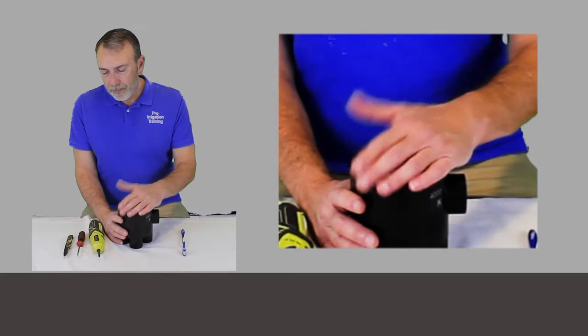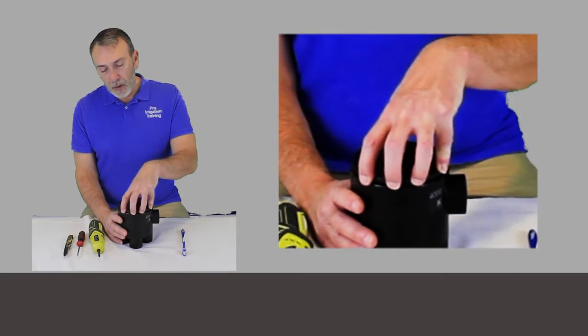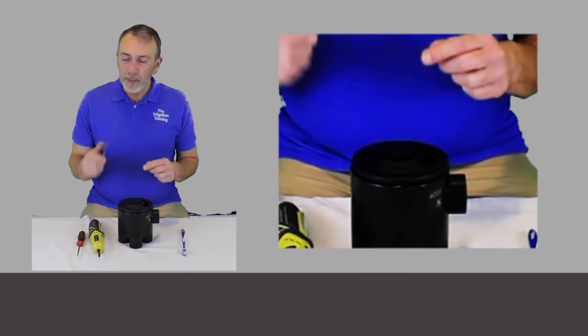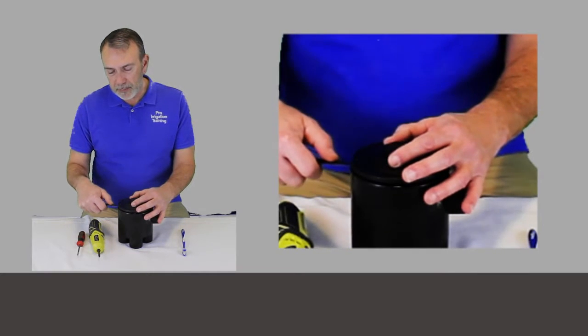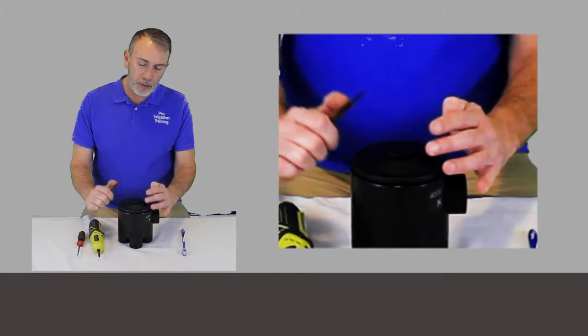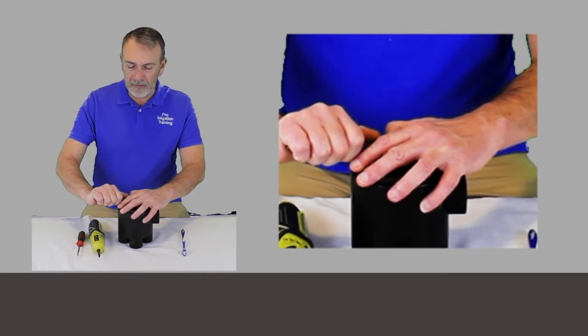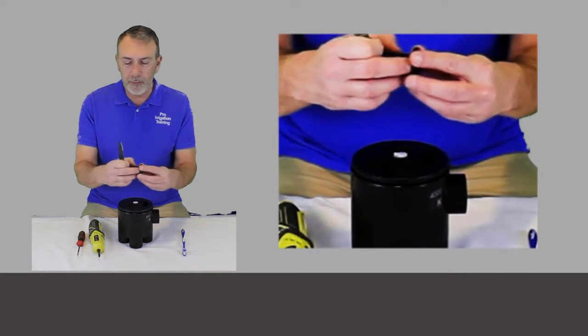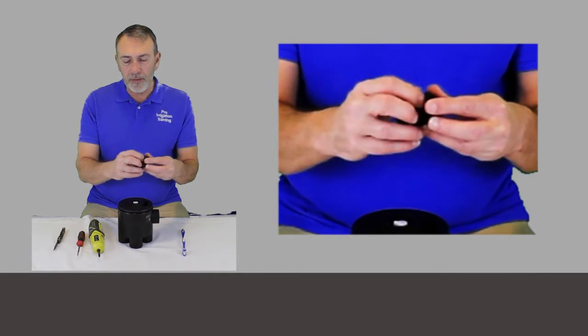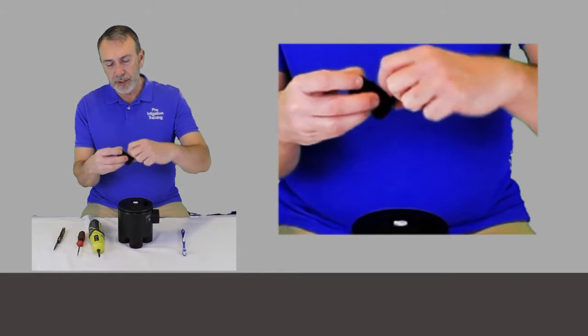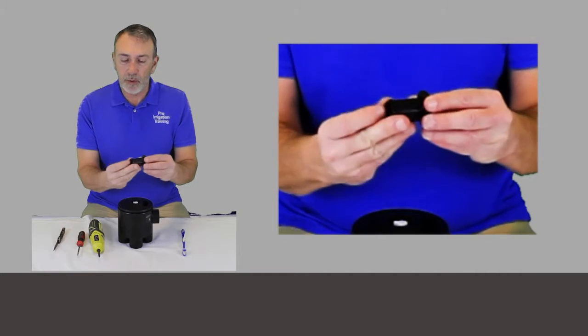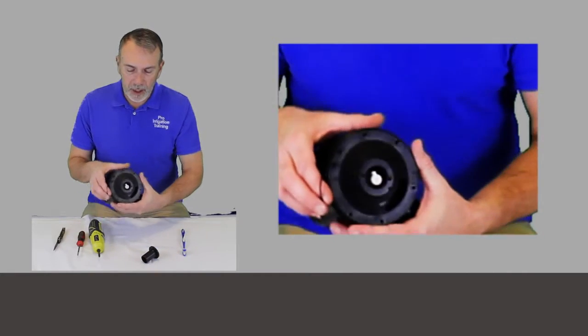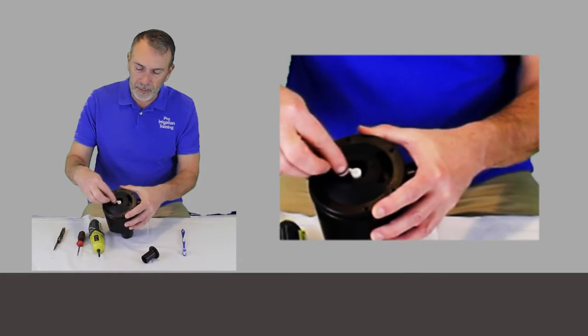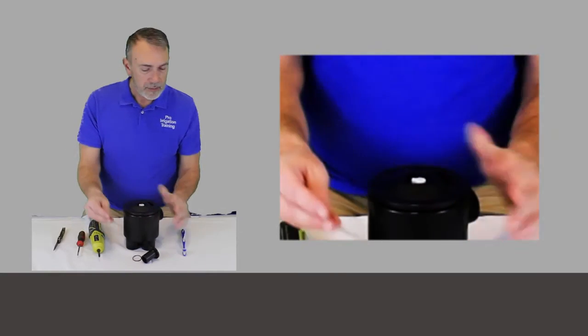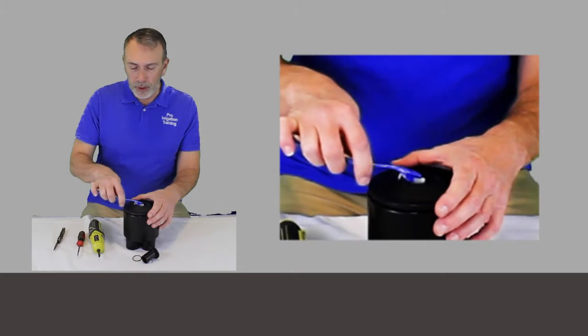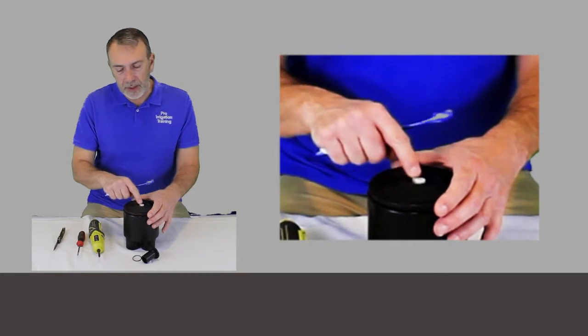So when you're taking this thing apart, if it's been there for a while, more than likely these parts are kind of seized together. We're going to see two different O-rings in here, but be careful if you're using a flat-bladed screwdriver or a knife to pry these pieces open. Make sure that you don't damage the O-rings underneath there, but a lot of times it's necessary to get a knife right under this lip and pry until it pops off, because the O-ring gets compressed and stuck down on there. This O-ring goes all the way up inside, just the corner of this. There's a little gap here, but that's not actually where the O-ring goes. It goes up against here, because when you look at the top, you see there's a little lip right at the very top of that entrance that this O-ring fits up against. So that's one of those areas when you're breaking this down where you'll want to make sure there's no grit or scale or sand or anything in there when you put it back together.